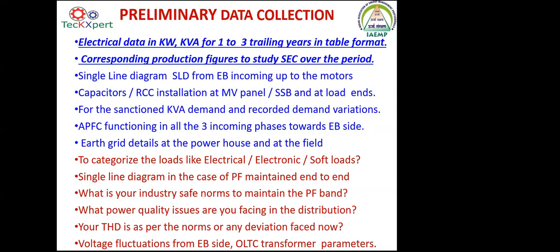The voltage fluctuations from the EB: if the powerhouse substation is very near or far off, or there are heavy fluctuations, this also has to be discussed with the electricity board authorities as well as the auditor. What has to be done? You have to give a background, with all the trend graphs, and submit it to the EB if there are heavy fluctuations due to loose connections at the incoming side. The OLTC of the industry has to be operating perfectly, and the counter set in the industry should be operating. All these readings you have to keep on record, so that once the auditor is there, he can see where you have maintained as per the norms and where the deviation is happening, go into it in depth, and make the corrections.